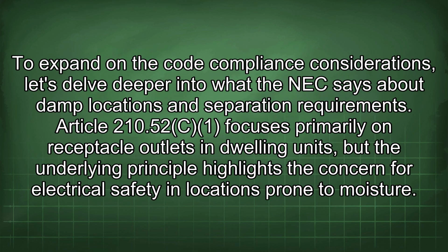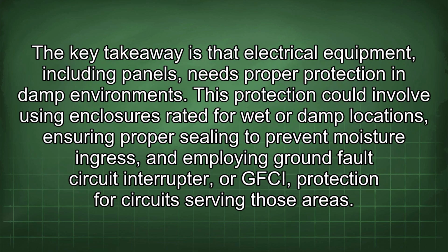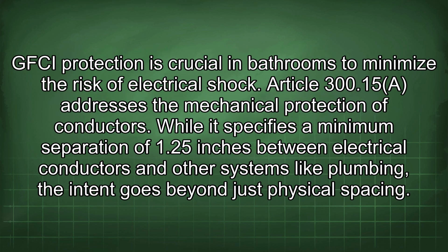To expand on the code compliance considerations, let's delve deeper into what the NEC says about damp locations and separation requirements. Article 210.52(C)(1) focuses primarily on receptacle outlets in dwelling units, but the underlying principle highlights the concern for electrical safety in locations prone to moisture. The key takeaway is that electrical equipment, including panels, needs proper protection in damp environments. This protection could involve using enclosures rated for wet or damp locations, ensuring proper sealing to prevent moisture ingress, and employing ground fault circuit interrupter, or GFCI, protection for circuits serving those areas. GFCI protection is crucial in bathrooms to minimize the risk of electrical shock.